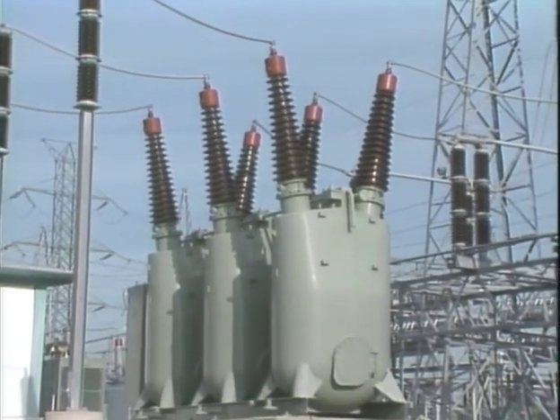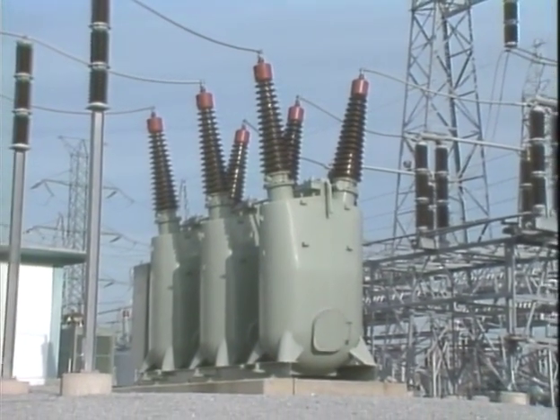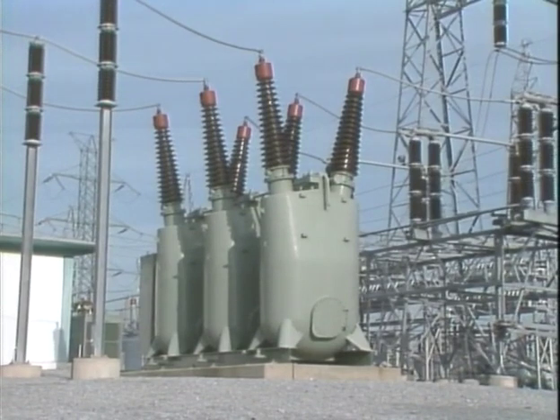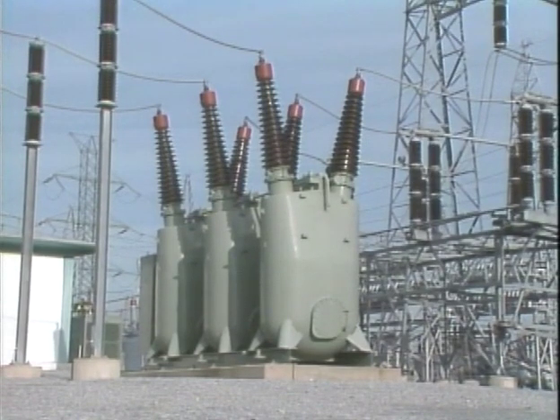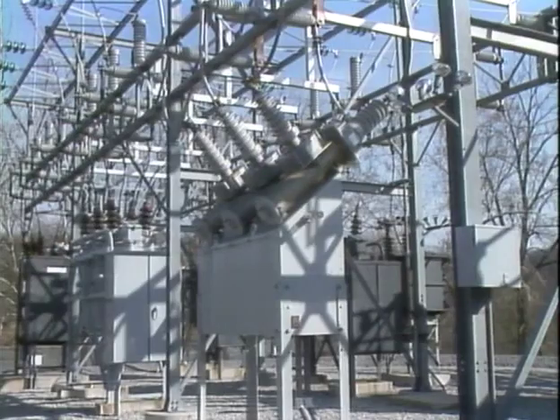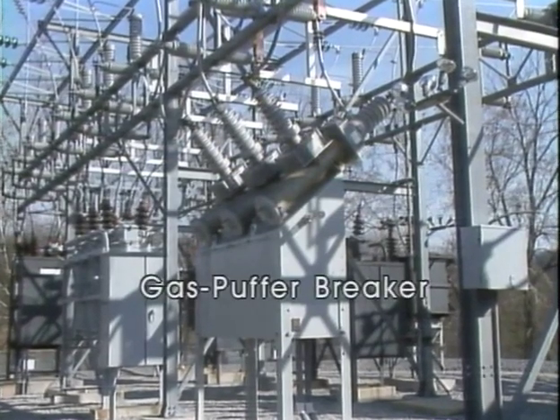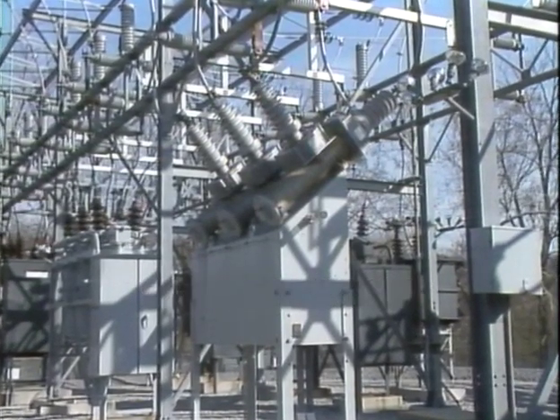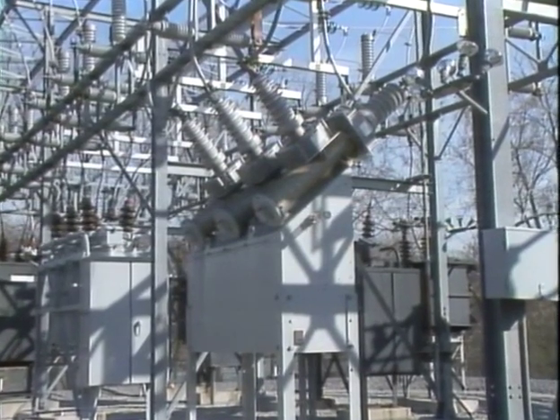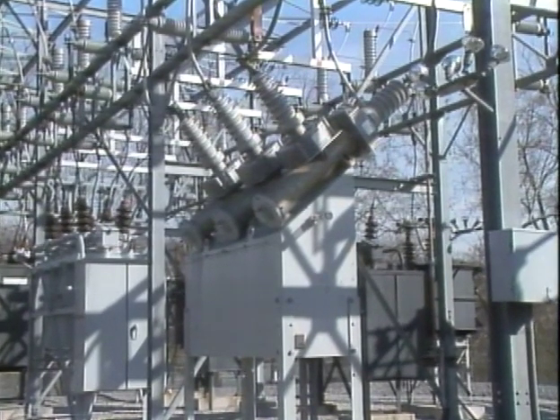The contacts of an oil breaker are submerged in an insulating oil, which helps to cool and extinguish the arc that forms when the contacts are opened. A fourth type of power circuit breaker is the gas puffer breaker. In a gas puffer breaker, the contacts are surrounded by low-pressure sulfur hexafluoride gas, commonly referred to as SF6 gas. At the moment that the contacts open, a small amount of gas is compressed and forced through the arc to stretch, cool, and extinguish it.